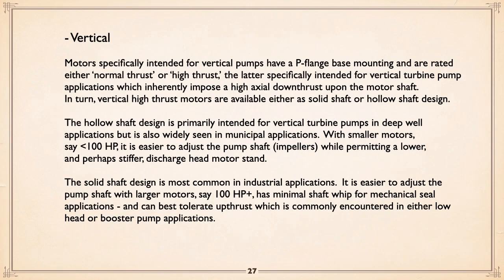Now, let's talk about vertical turbine pumps. You can get normal thrust, which some sewage pumps use, but it's kind of rare nowadays. But the moment you say high thrust, now you're talking vertical turbine country, because the pump has inherently, as we saw before, an awful lot of axial thrust downward. Okay, so the vertical turbine motors are designed to have that high thrust capability.